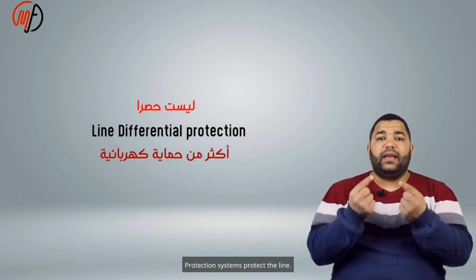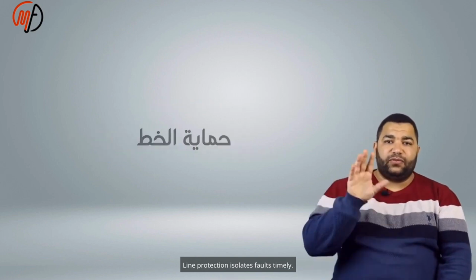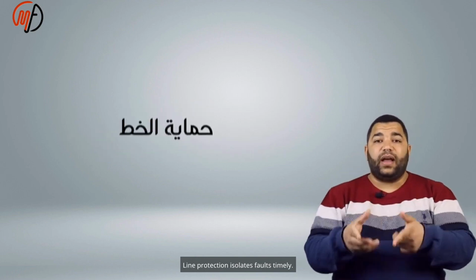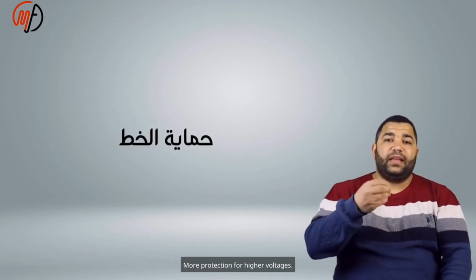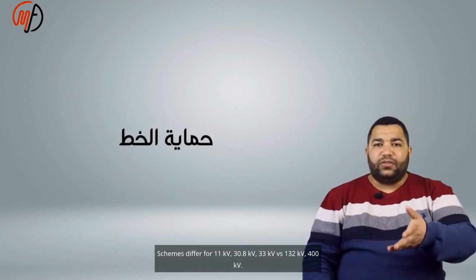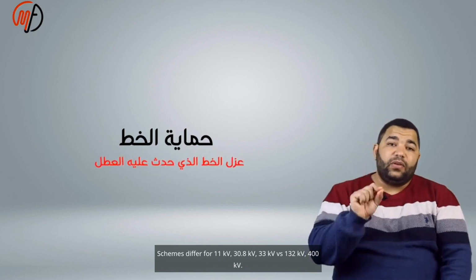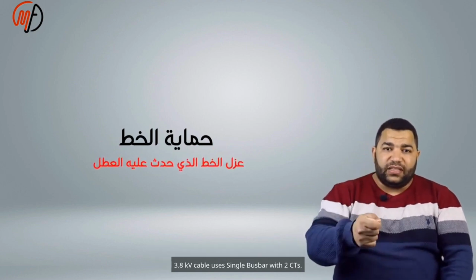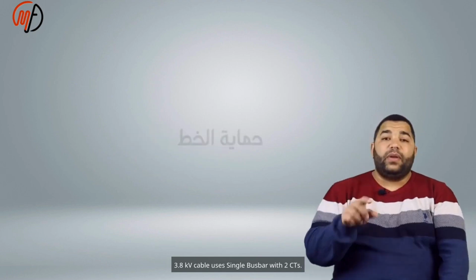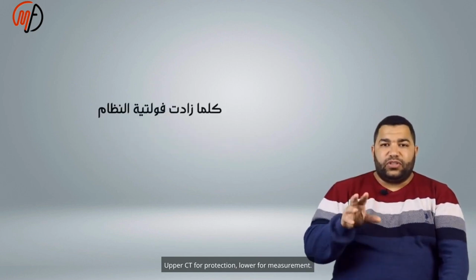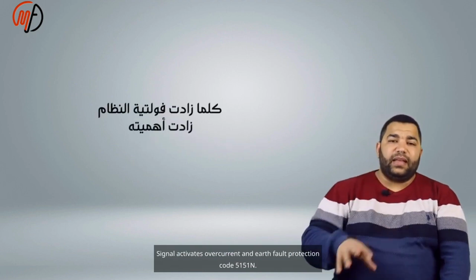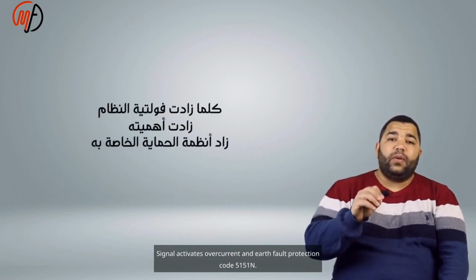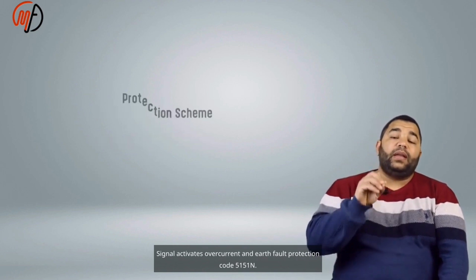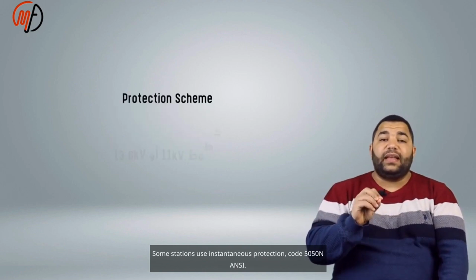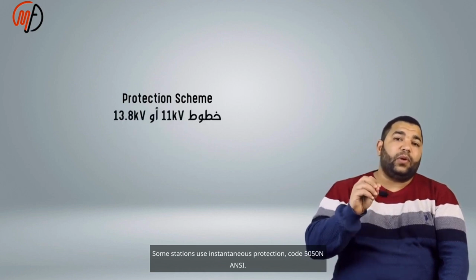Protection systems protect the line. Line protection isolates faults in a timely manner. More protection is needed for higher voltages. Schemes differ for 11 kV and 33 kV versus 132 kV and 400 kV. A 13.8 kV cable uses a single bus bar with two CTs. The upper CT is for protection, the lower for measurement. The signal activates overcurrent and earth fault protection, code 51/51N. Some stations use instantaneous protection, code 50/50N ANSI.